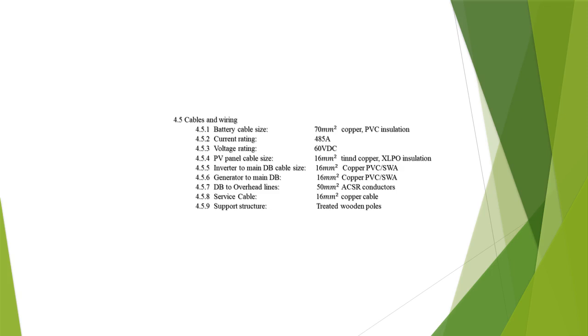Then on the cables and wiring, on the batteries the cable size would be 70 square millimeter copper with PVC insulation, and the current rating will be 485 amps, voltage rating 60 volts DC, and PV panel cable size should be 16 square millimeter tinned copper with XLPO insulation. And the cable that's going to be used from the inverter to main DB should be 16 square millimeter copper PVC steel wire armored cable. And from the generator to main DB, it will be 16 square millimeter copper PVC steel wire armored cable.